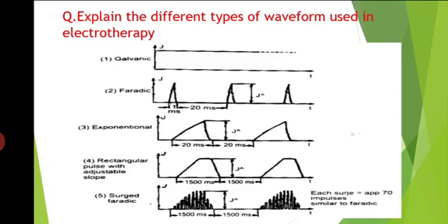Faradic current. Faradic current is a sequence of pulses with a defined shape and current intensity. The pulse duration is about 1 millisecond with a triangular waveform, and the interval duration is about 20 milliseconds. Faradic current acts upon muscle tissues and, upon the motor nerves, produces muscle contraction. There is no ion transfer and no chemical effect. It is used in the treatment of muscle weakness.